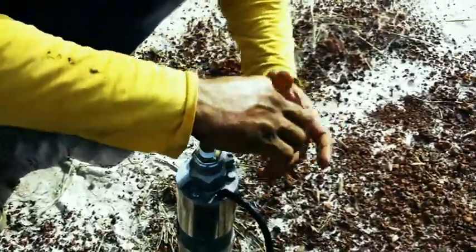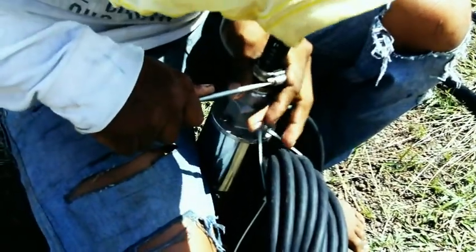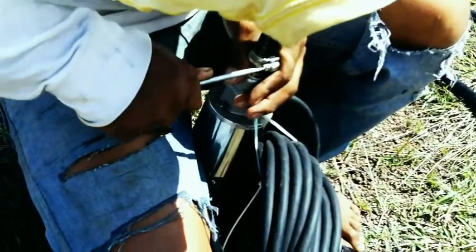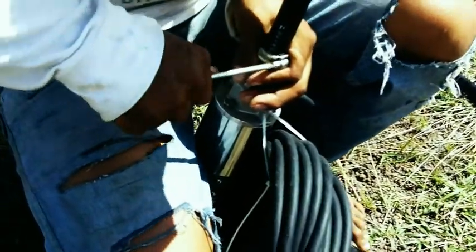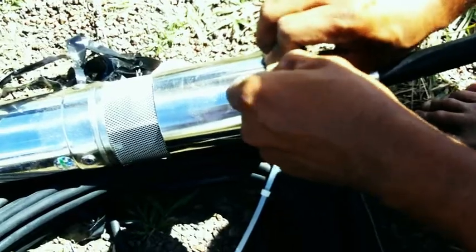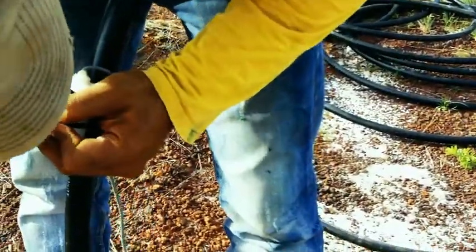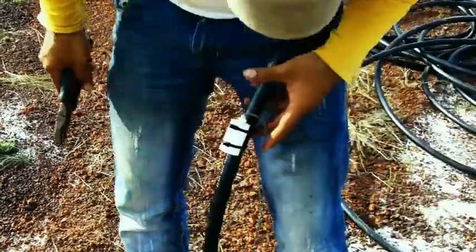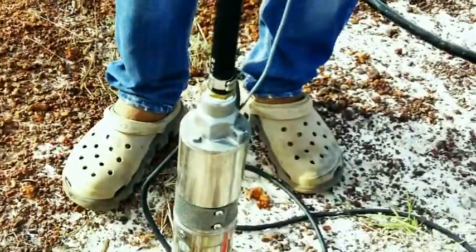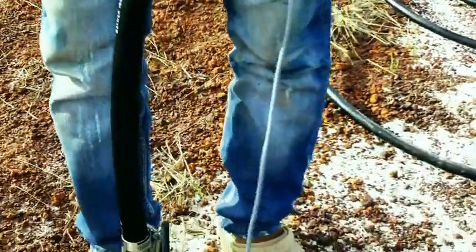Next, the submergible pump was prepared with Teflon tape, the hose secured at the top, and a safety cable retrieval line hooked into place. The water sensor was attached approximately 1 foot above the pump level to finish off the submergible portion. We then carefully lowered the pump into place down the well.